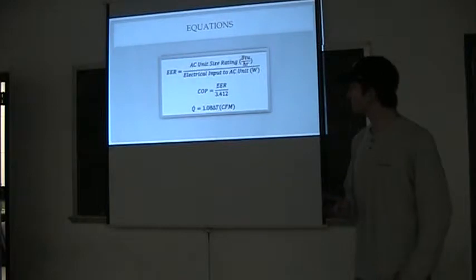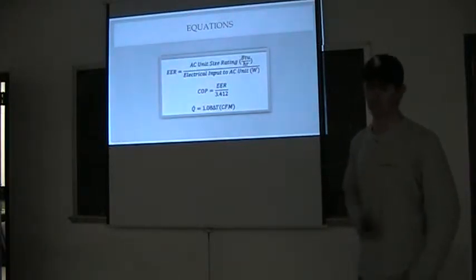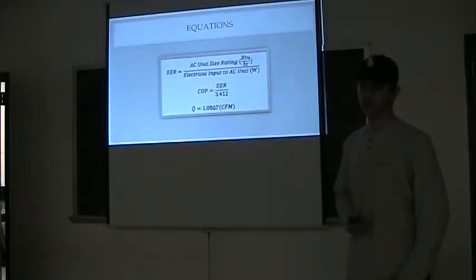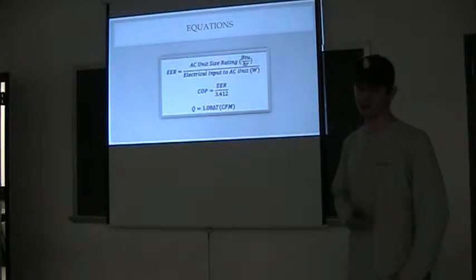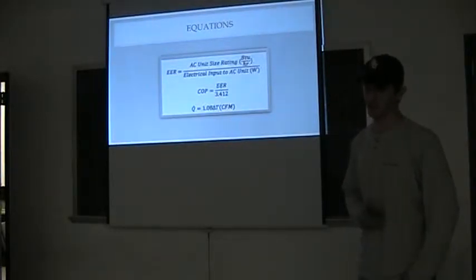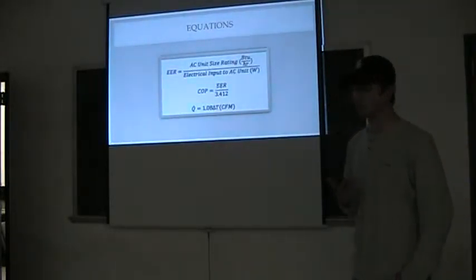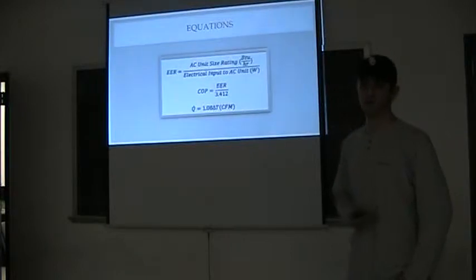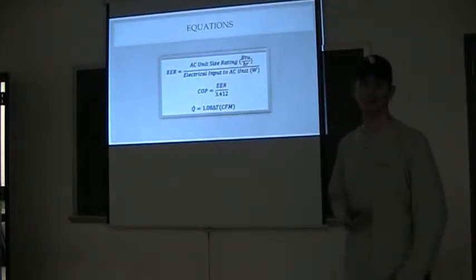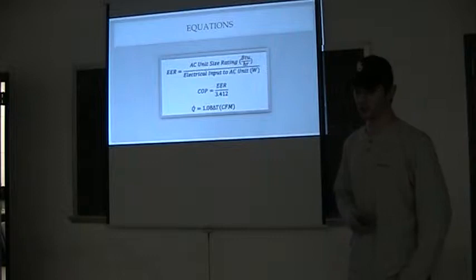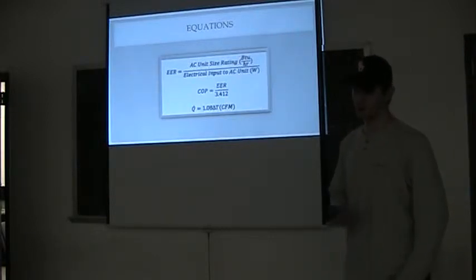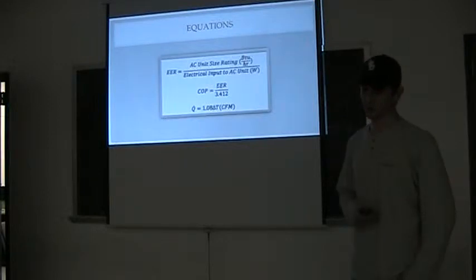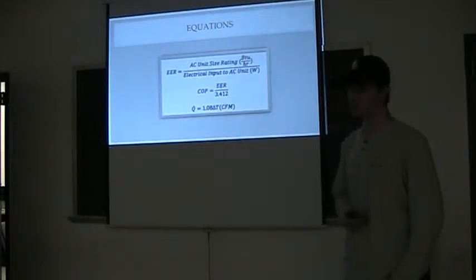The main equations used are the EER, which is the energy efficiency ratio. It's the AC unit size rating divided by the electrical input in the AC unit. Next, we have COP, which is the coefficient of performance. This is the energy efficiency ratio divided by 3.412. And then Q dot is the rate of heat removal, which is equal to 1.08 times the change in temperature times the volumetric flow rate.